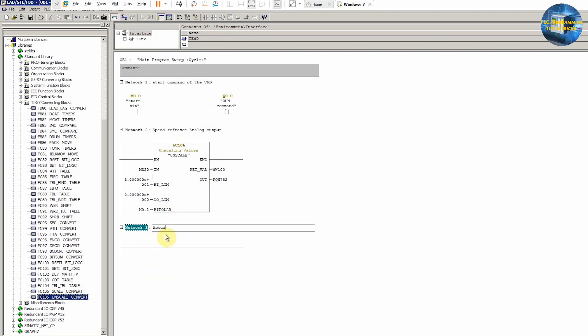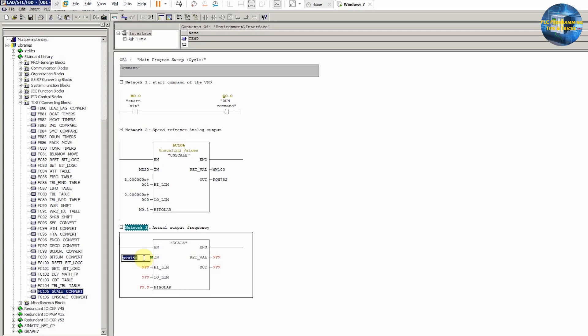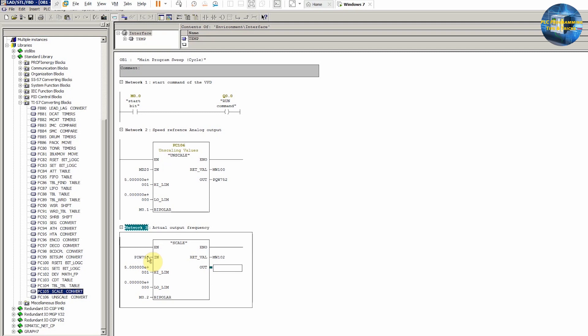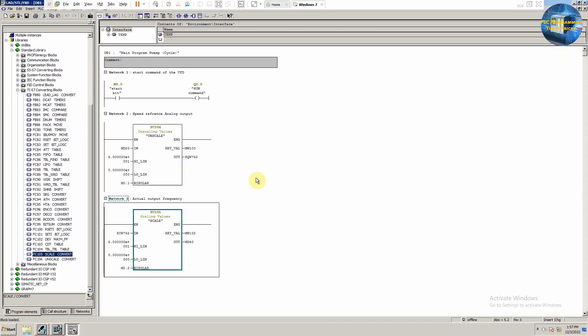PQW752 will send the output analog signal to channel 0 of the PLC. In network 3 we will make logic to read the analog signal of the actual output coming from the VFD. For reading the analog signal we will use the scale function FC105. We will enter PIW752 — the data register holding the values for analog input channel 0. This value can be scaled from 0 Hz to 50 Hz by entering 0.0 and 50.0 in the low and high limits. Finally we enter MD40 as the output of the scale function, so the actual output frequency of the VFD is stored in MD40.